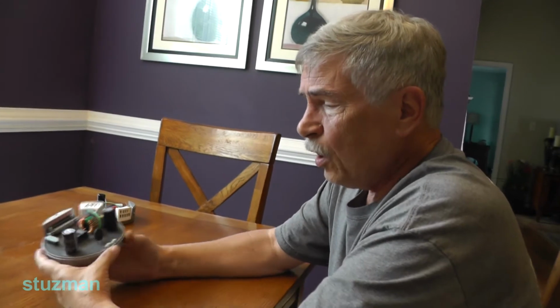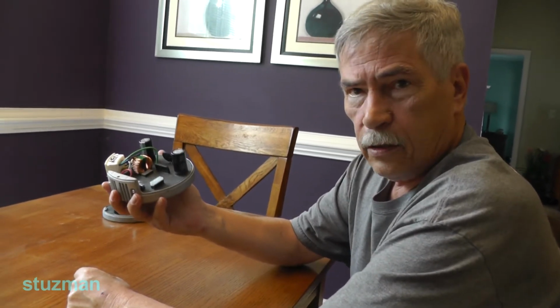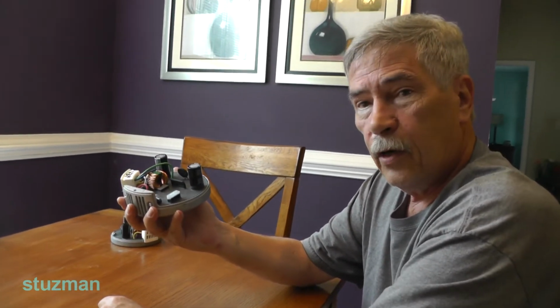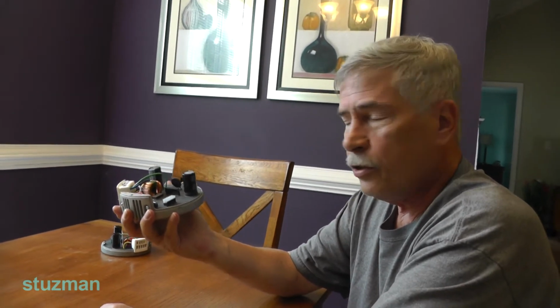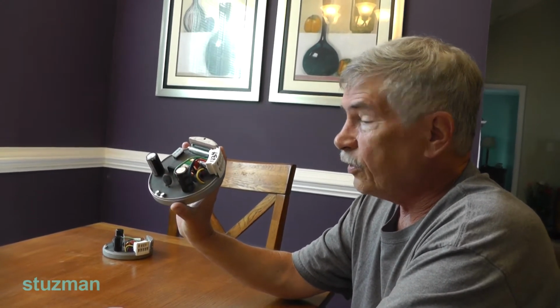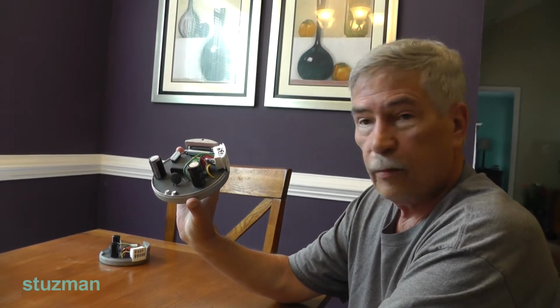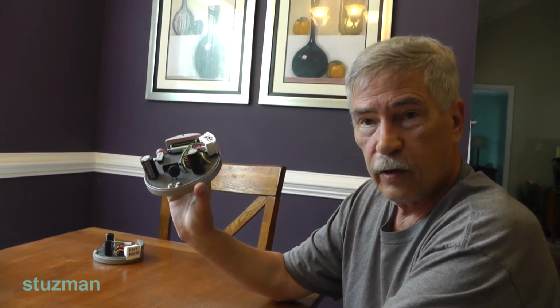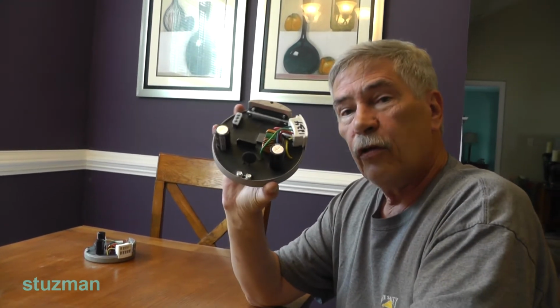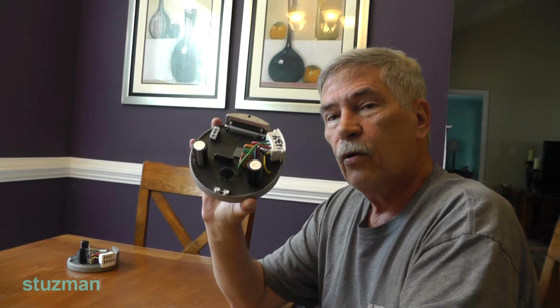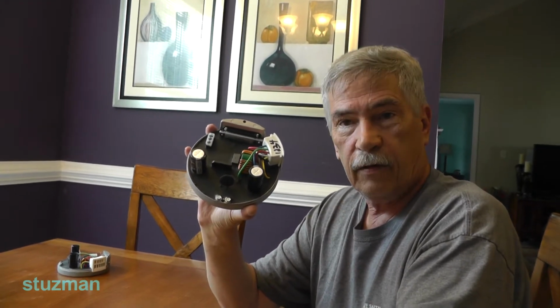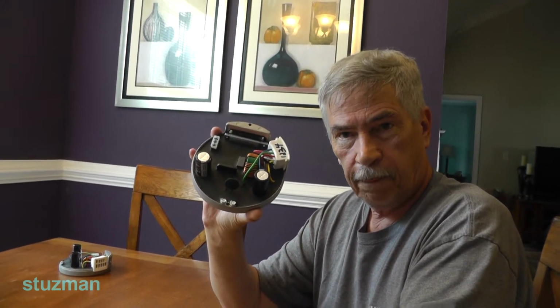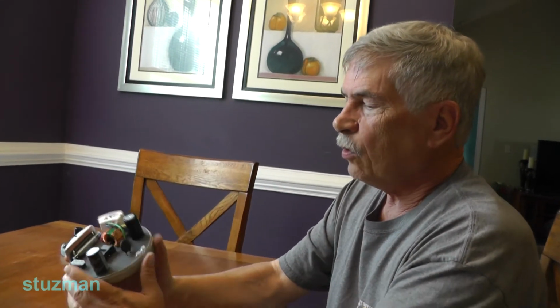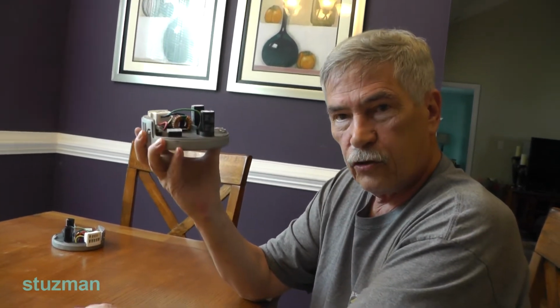Let me tell you about another thing that can happen. Now, the rotation of the motors - depending on how the air handling unit is, whether it's horizontal or vertical, you remember how the squirrel cage goes in there, it's possible that the motor might need to go the other way. So with this being out of another unit, it could be that this motor is totally backwards from what we have, and the rotation is going to be wrong, right? My understanding of how that works is that the rotation is not programmed into the motor initially.